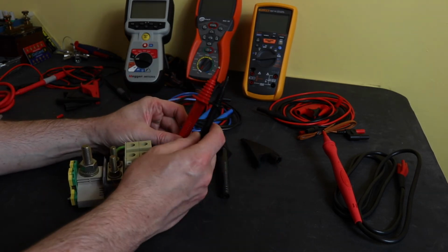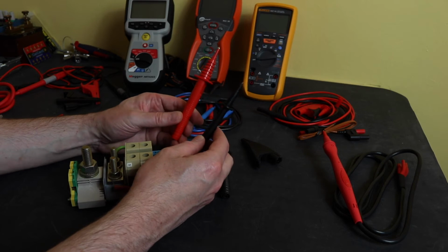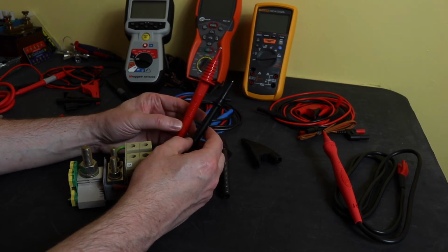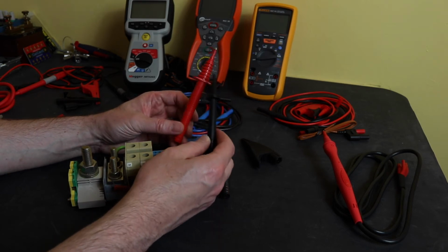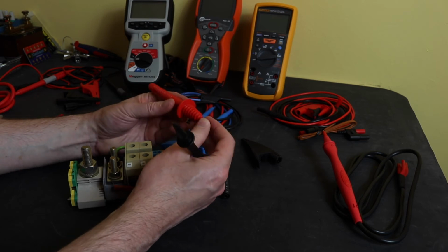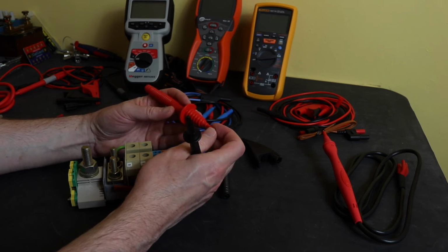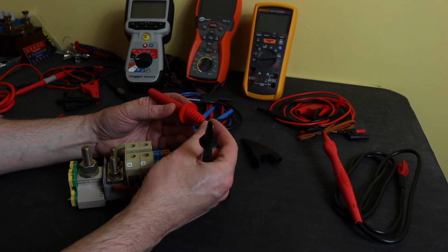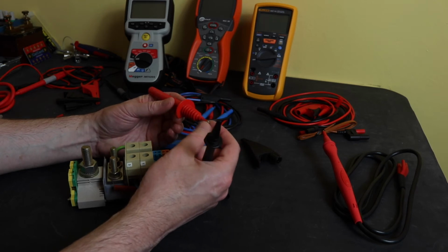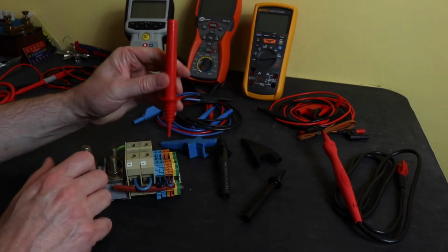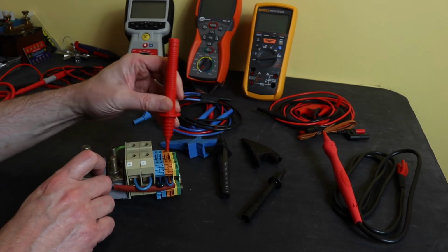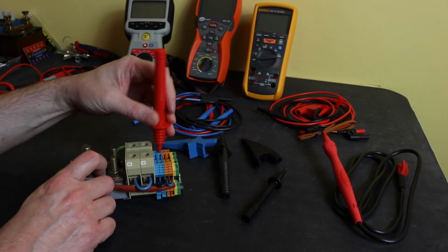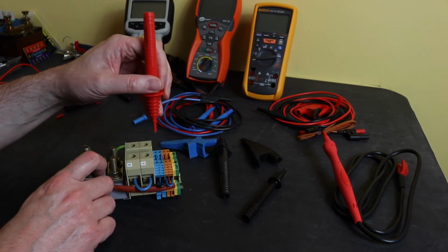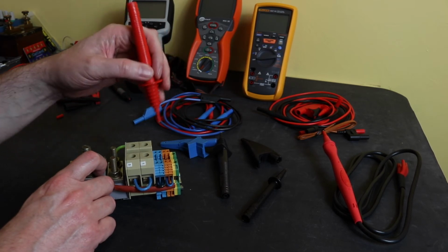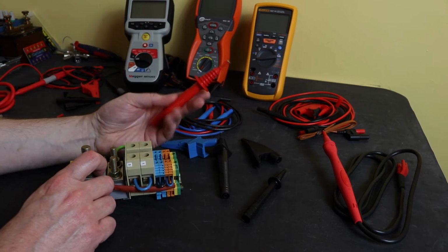Sonel have a slightly different approach. They are a much beefier, much bulkier probe. They are standard probes, they're not fused. They are quite wide tipped here, and as per the Megger, the insulation is fixed. There's no removable aspect to that. You cannot get in a 2.5, you can get in a 4. So that's one up from the Fluke probe tips, but not quite as good as the Megger ones.